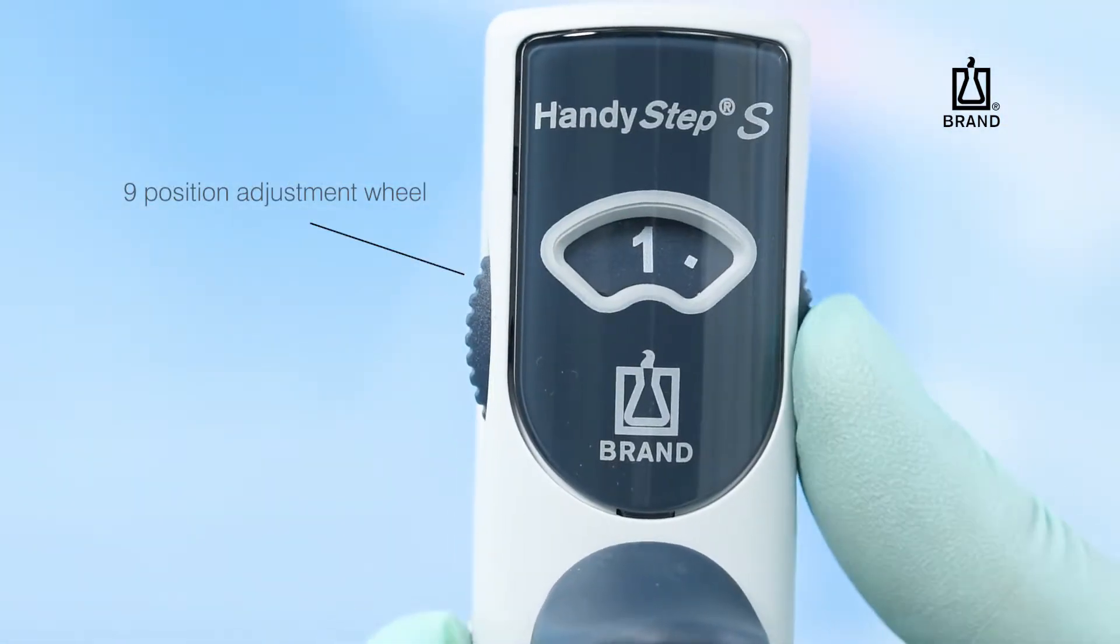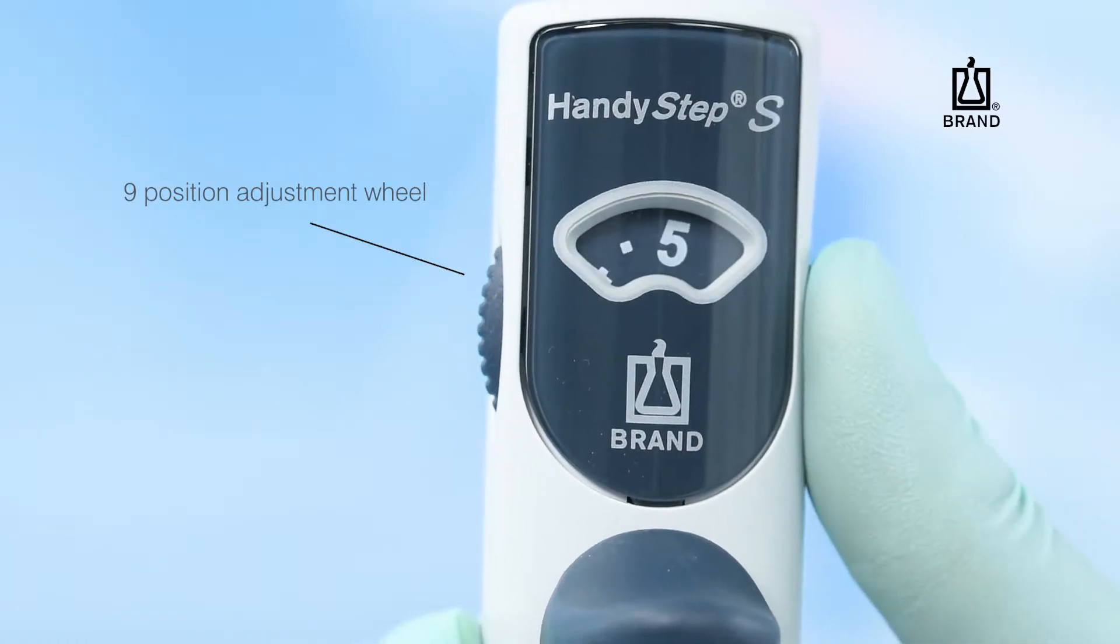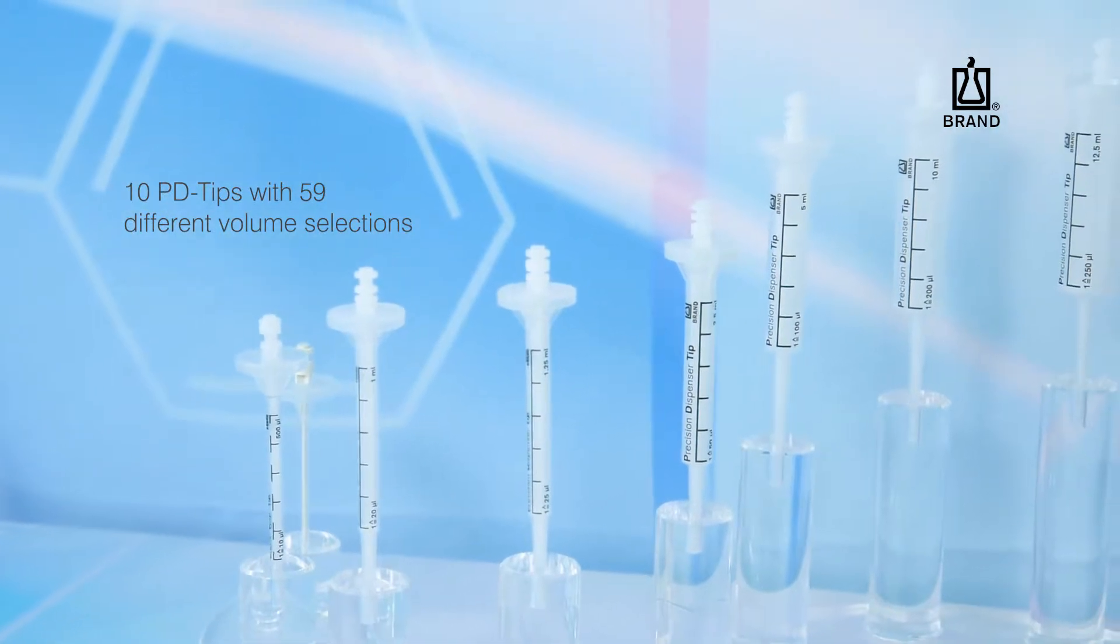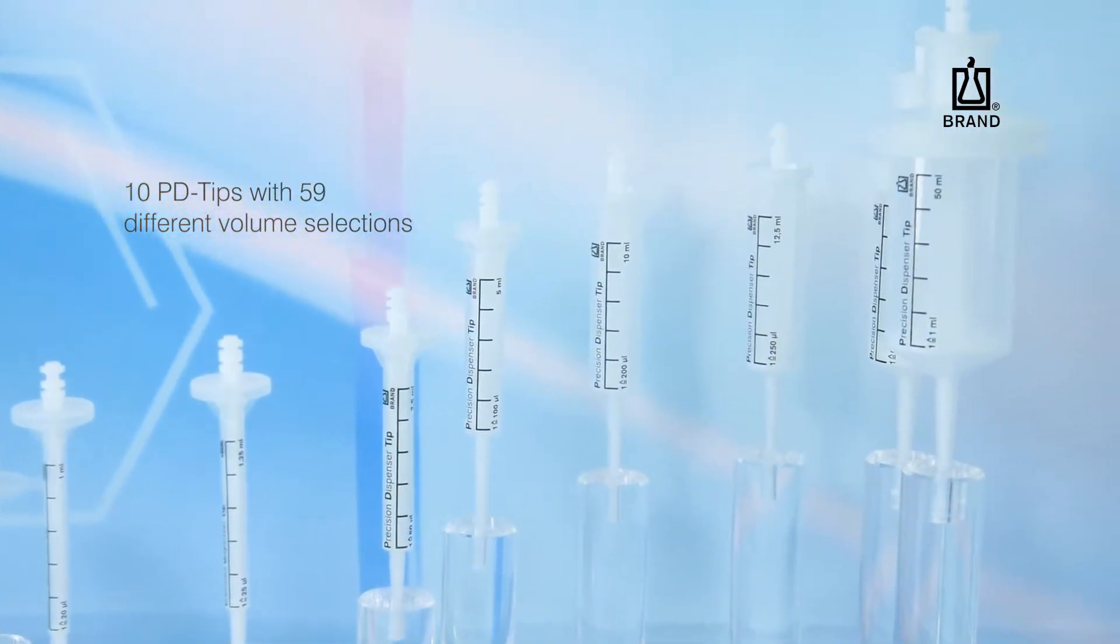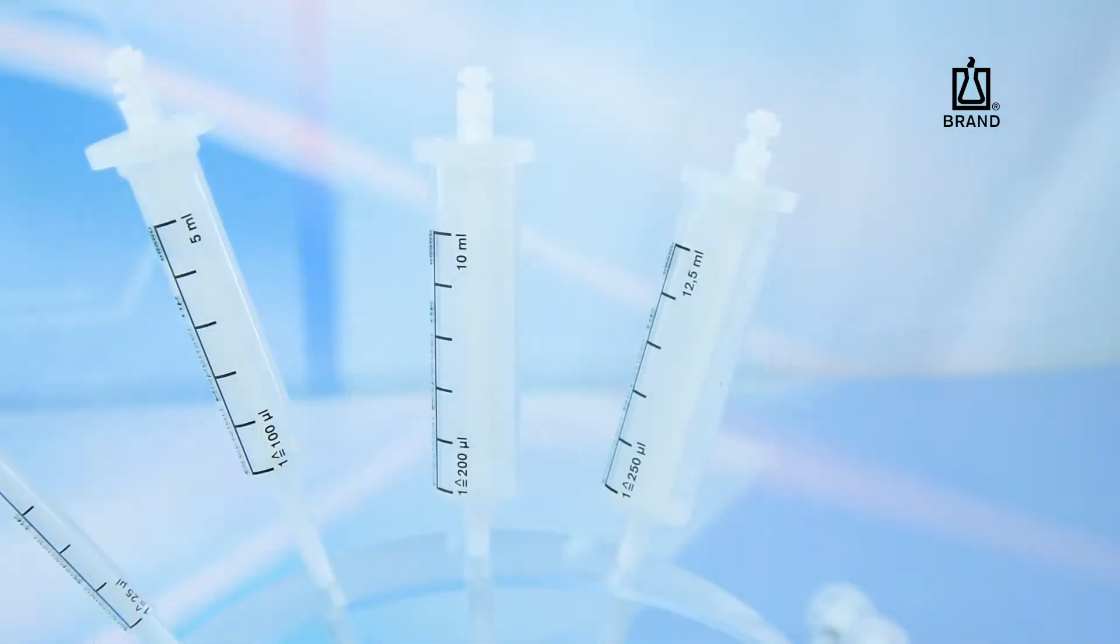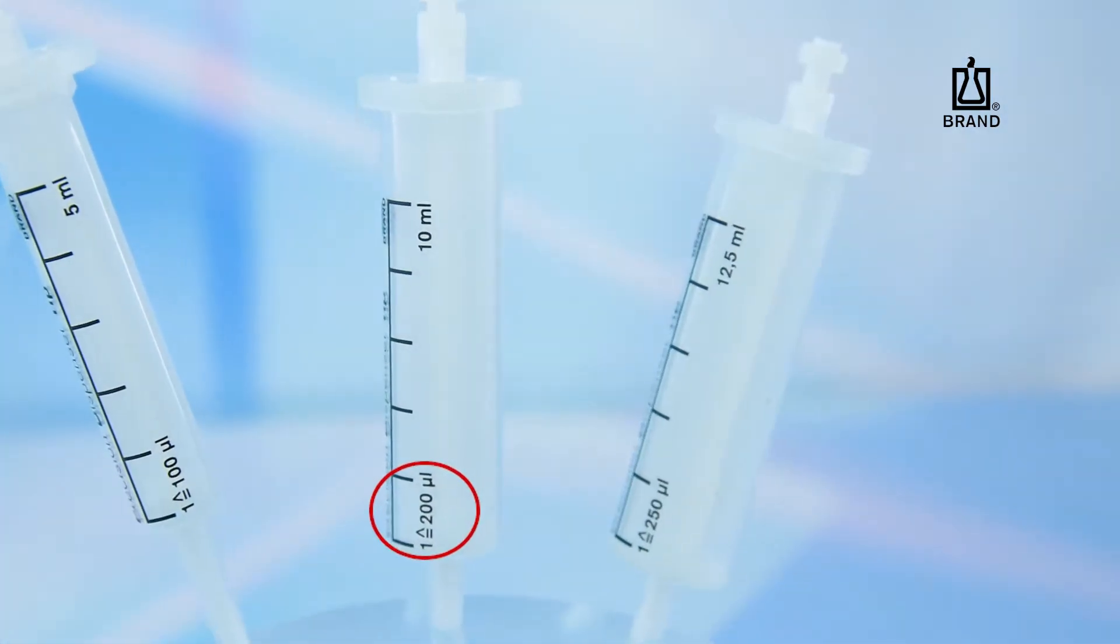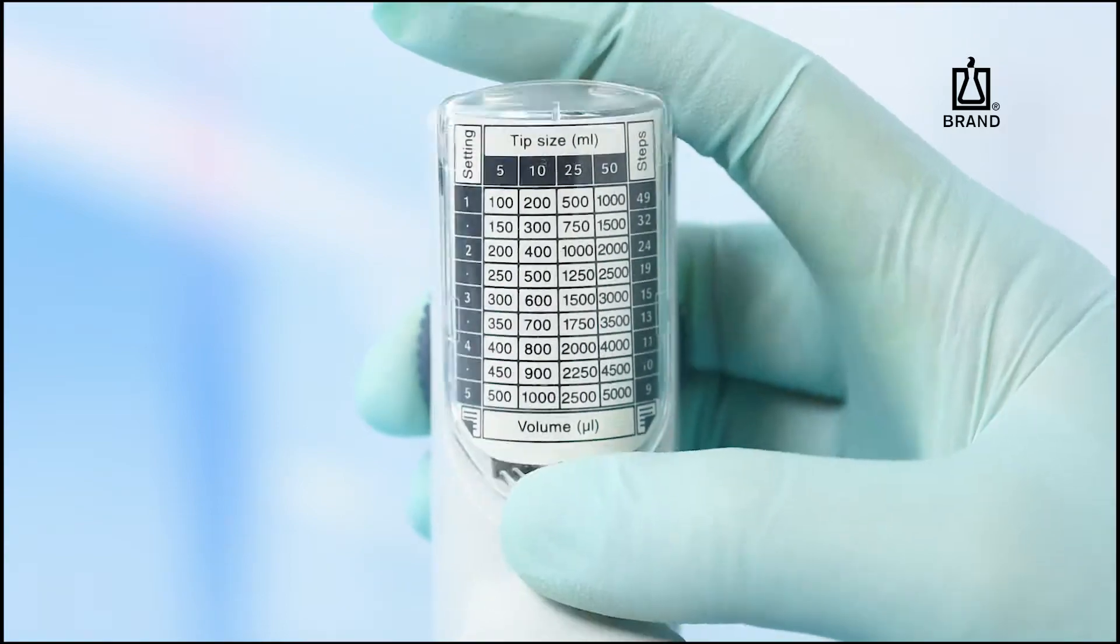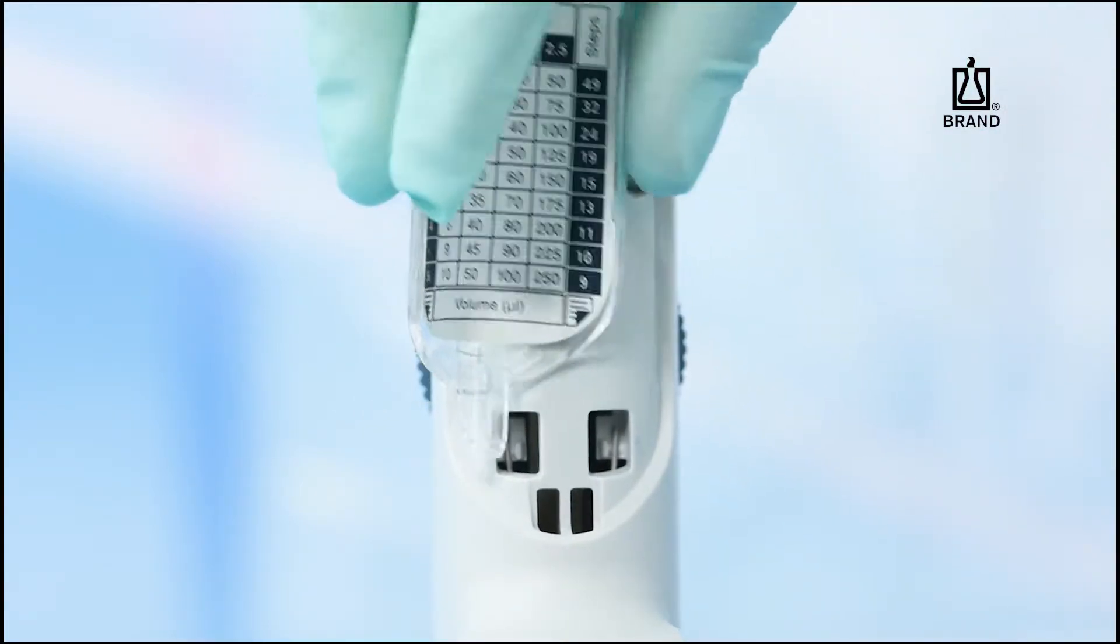The HandyStep S features a nine-position adjustment wheel with settings from one to five in half-step increments. When used with the 10 different sized PD Precision Dispenser tips, there are 59 different volumes that can be selected. To determine the volume dispensed, note the partial volume printed on the PD tip and multiply it by the settings shown on the adjustment wheel. Alternatively, a two-sided chart on the HandyStep S provides a convenient reference.